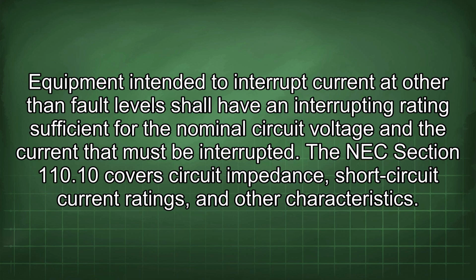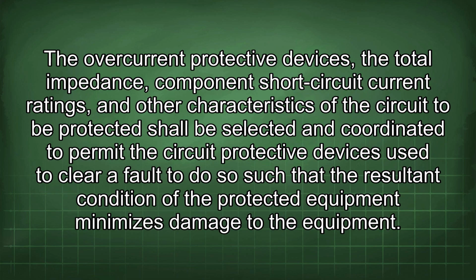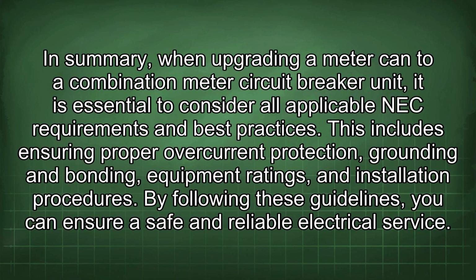The NEC Section 110.10 covers circuit impedance, short circuit current ratings, and other characteristics. The overcurrent protective devices, the total impedance, component short circuit current ratings, and other characteristics of the circuit to be protected shall be selected and coordinated to permit the circuit protective devices used to clear a fault to do so such that the resultant condition of the protected equipment minimizes damage to the equipment. In summary, when upgrading a meter can to a combination meter circuit breaker unit, it is essential to consider all applicable NEC requirements and best practices.